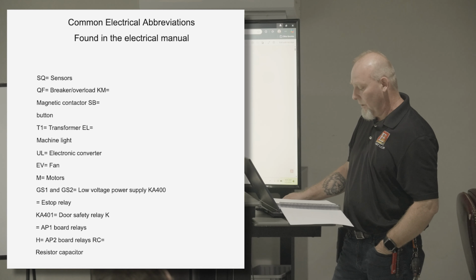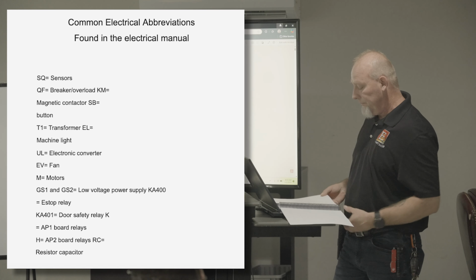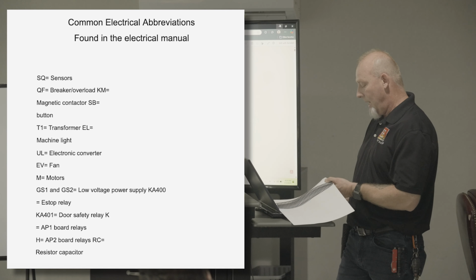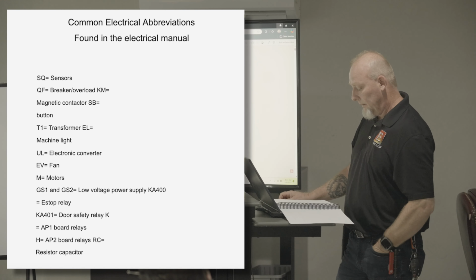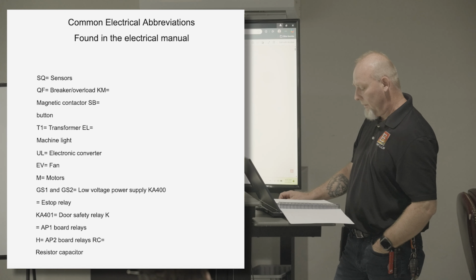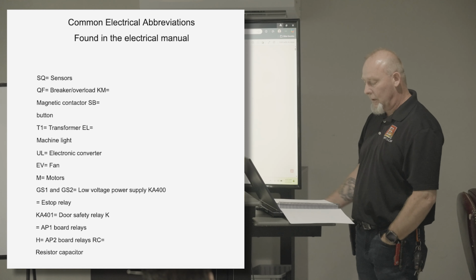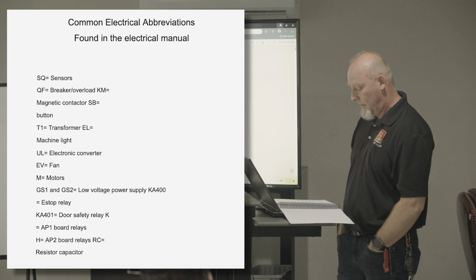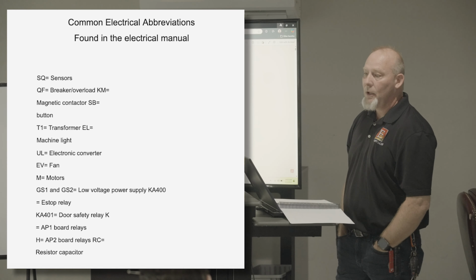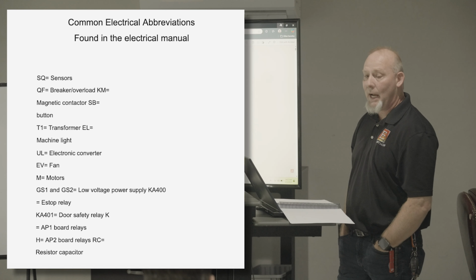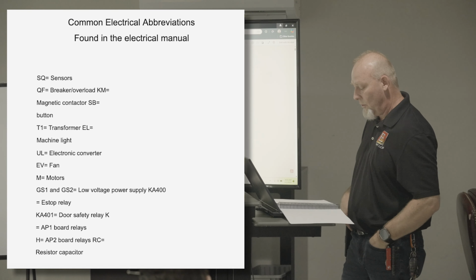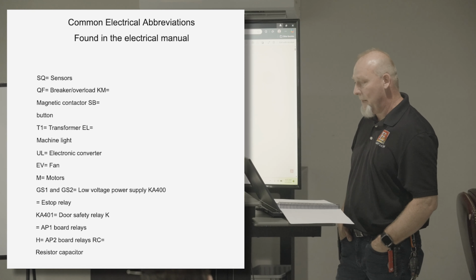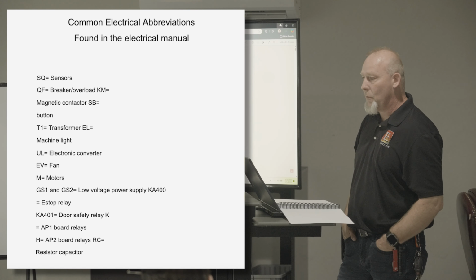QFs are for breakers, overloads, KMs are magnetic contactors, SBs are buttons. The T1 is transformer, EL is our inside light, UL is electrical converters, EVs are fans, M's are for motors. GS1, GS2 is your low voltage control power supplies, your 24 DC. GS1 is typically your voltage for the drives and NC, and the GS2 is for your working voltage, which would be either AP1 or AP2. It's going to manage all the voltage for your solenoids.